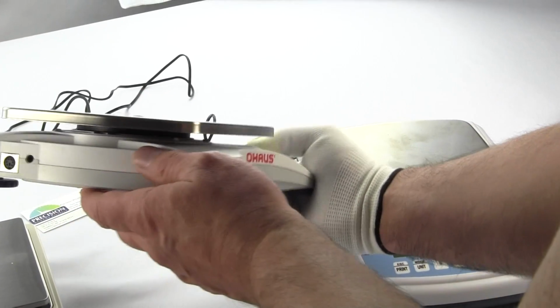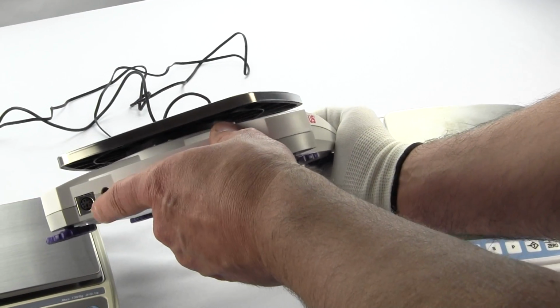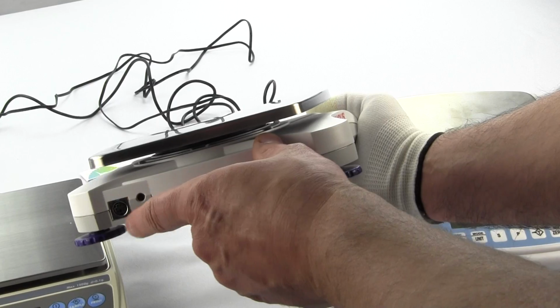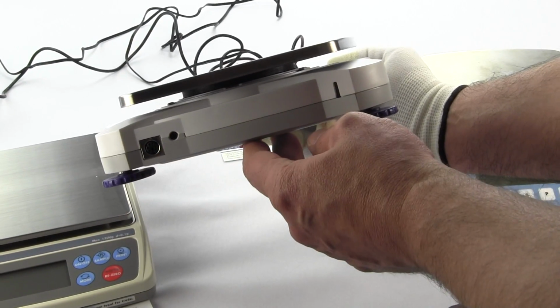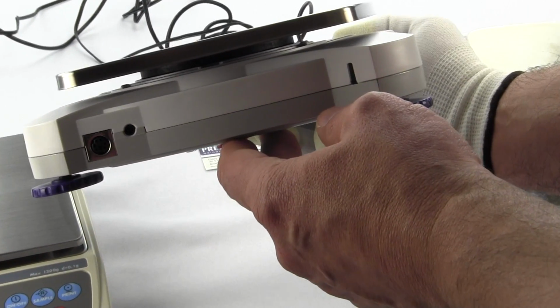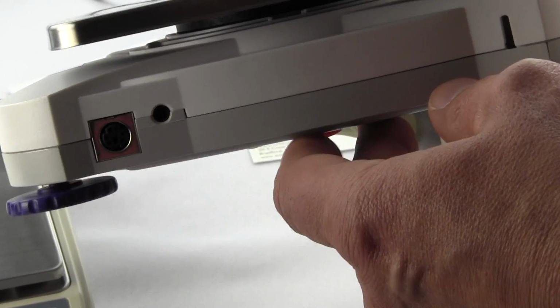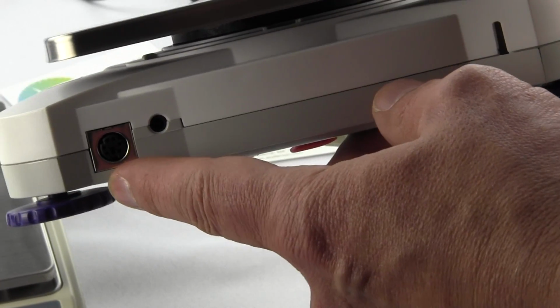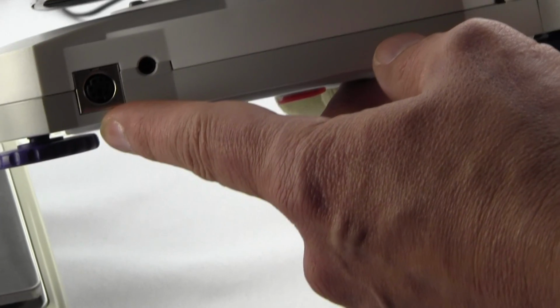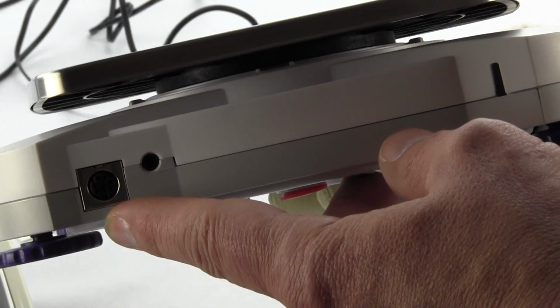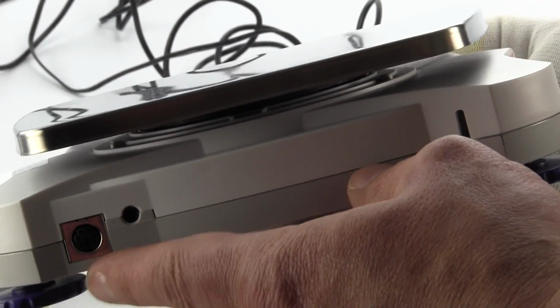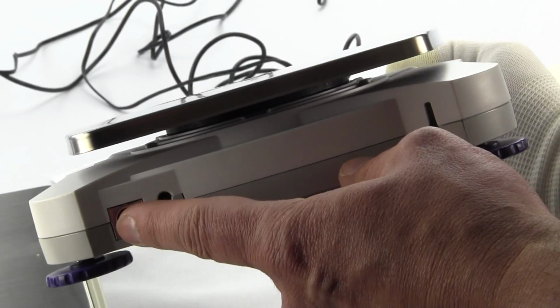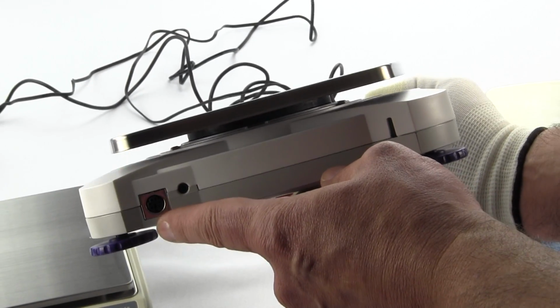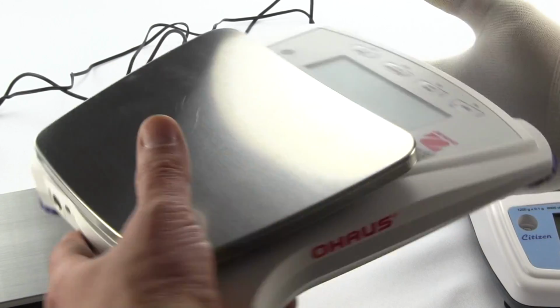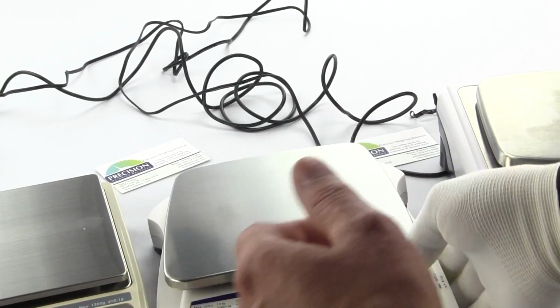On the Ohaus, if you look on the back, there's like a DIN connector. This is not an RS-232. They have modules that you have to pay for. They're extra. It's an optional accessory. They have a USB, they have a Bluetooth, they have an Ethernet connection. They start at about, I think, $90, and they go up to about $240, depending upon what kind of communication. So with Ohaus, it's an option. It does not come standard.